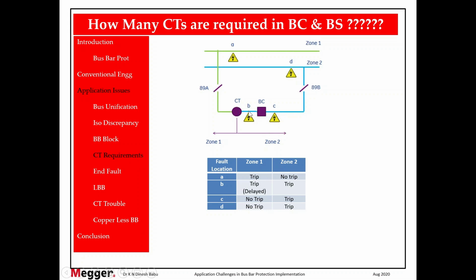Whenever there is a fault in the blue region, it will trip all the bays and it will open the bus coupler. The moment the bus coupler is open, this fault is still fed by zone 1. Now what the relay will do is monitor the status of the bus coupler. Whenever the bus coupler is open and there is a fault in the bus coupler CT, it will trip zone 1. So this logic is implemented in the numerical relay. That means you don't need 2 CTs. With 1 CT itself, you can still do it. However, there is a trip delay. What is the delay? The delay is the breaker operation time.